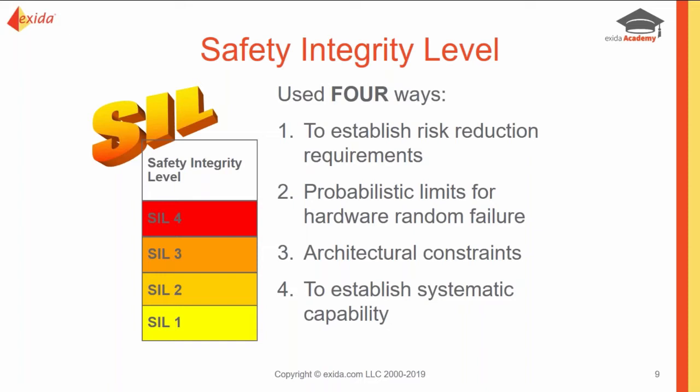End users can use the IEC 61511 standard and figure out, with the SIL rating, the risk reduction requirements for their system, the probabilistic limits for random hardware failures, the architectural constraints, and the systematic capability. All of these are very important to end users to know that they are removing enough risk.